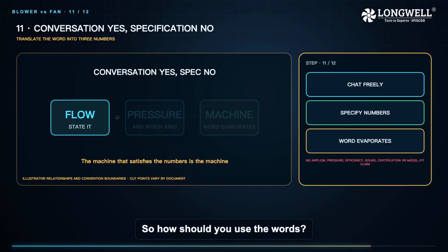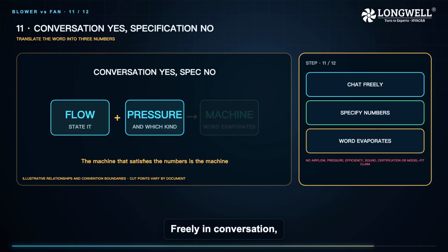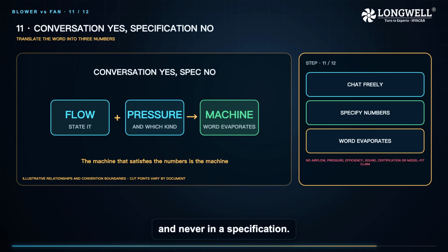So how should you use the words? Freely in conversation, and never in a specification. When it is time to buy, translate the word back into what it was always hiding: the airflow you need, the pressure your system imposes, and which kind of pressure that figure is. Those three numbers make the fan versus blower question evaporate, because the machine that satisfies them is the machine, whatever the label on its catalog page says.